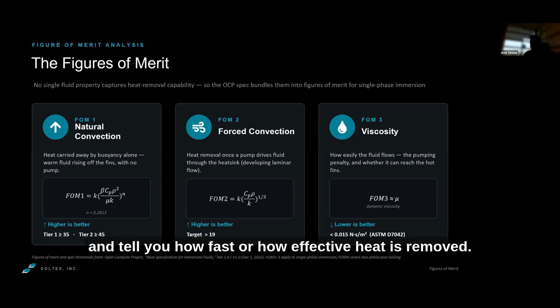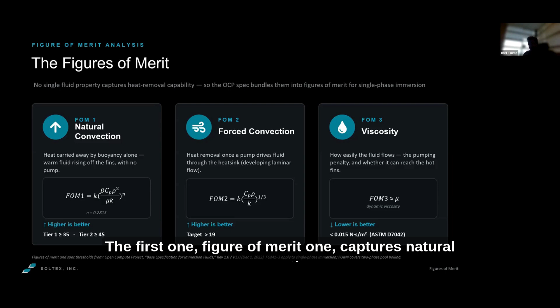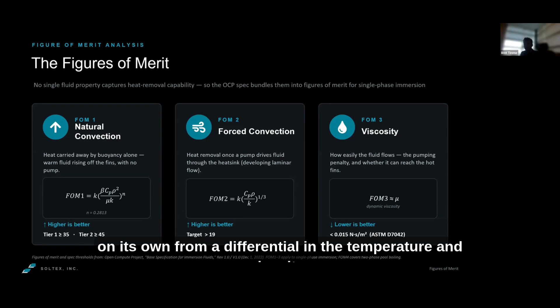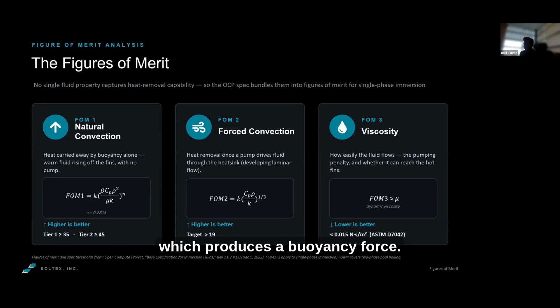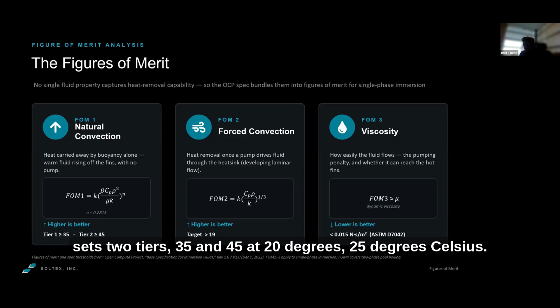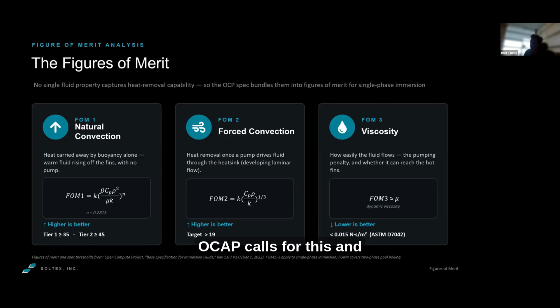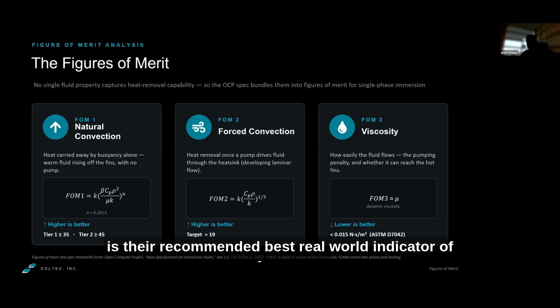heat is removed. The first one, figure of merit 1, captures natural convection. Heat is carried away by the fluid rising off the components on its own, from a differential in temperature and density, which produces a buoyancy force. There's no pump involved. Higher is better. The spec sets two tiers, 35 and 45 at 25 degrees Celsius. OCP calls for this and it is their recommended best real-world indicator of performance.